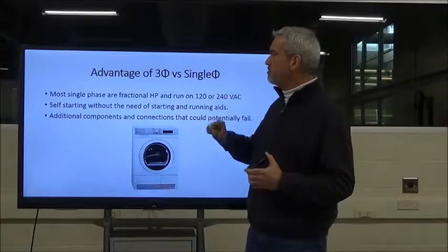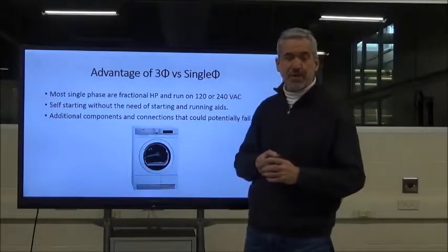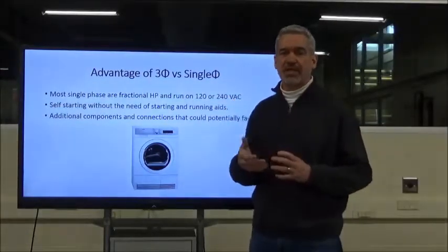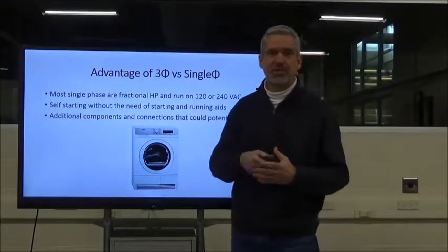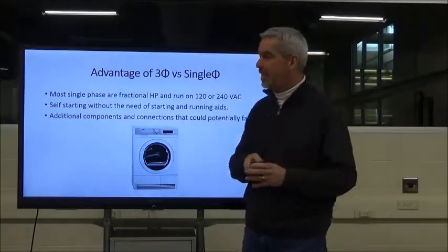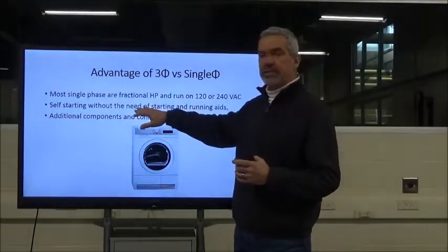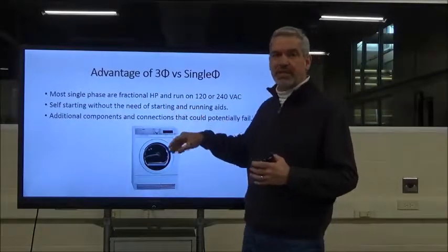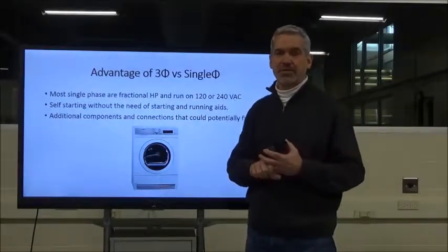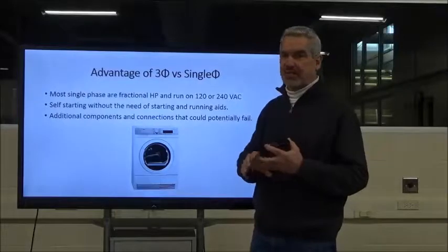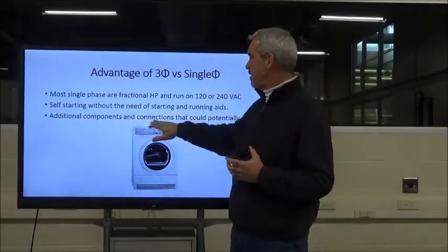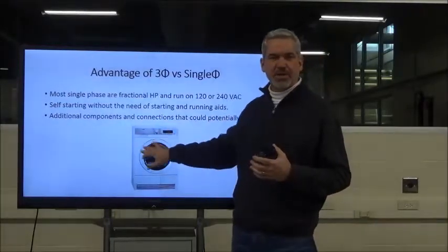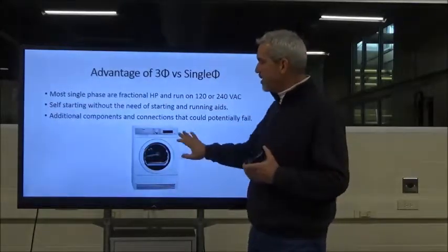Most single-phase motors are fractional horsepower and typically run on 120 or 240 volts — you see a lot of these in your home, like your washing machine or dryer. The AC induction motor is self-starting; we don't need starting aids such as capacitors and additional start windings. Those are potential points of failure that we eliminate with a three-phase motor.